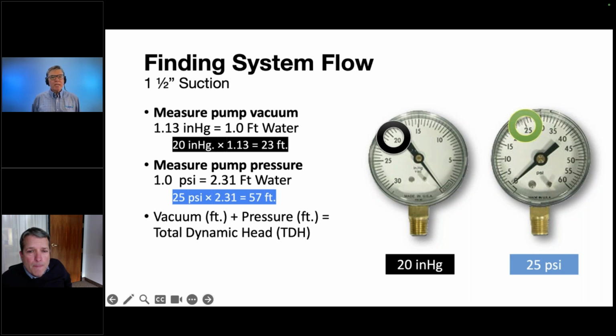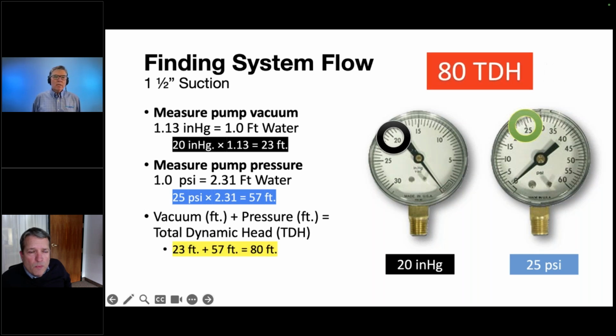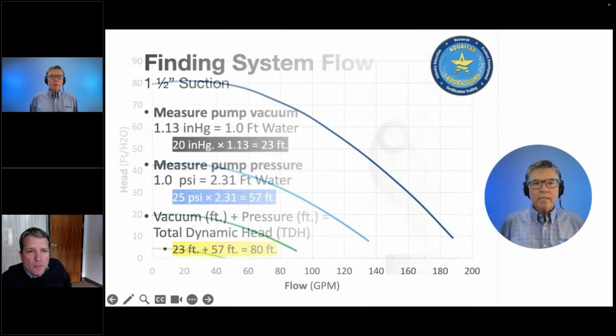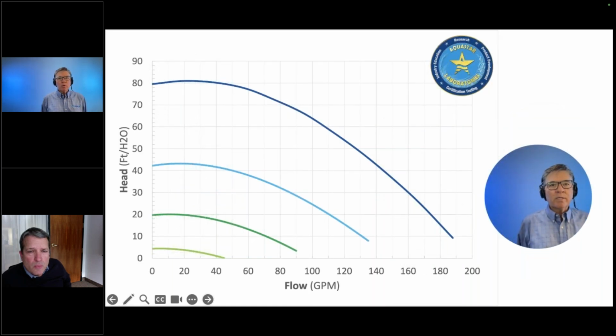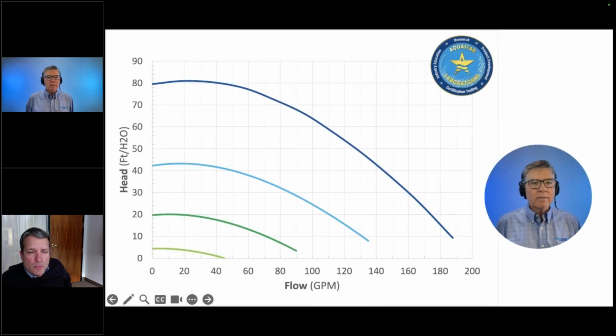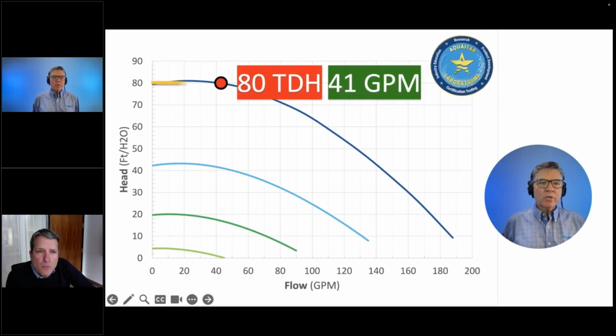The same process here, but when we do this calculation, we went from 50 to 80 TDH. Most of this is on the suction side, so we're in cavitation. This pump will run here for a while, but not a lifetime. Same process: we find it on the curve. This is our new flow rate.